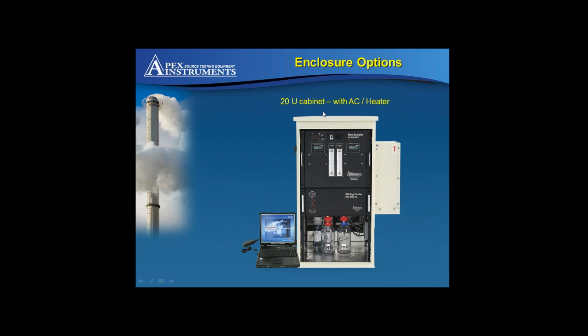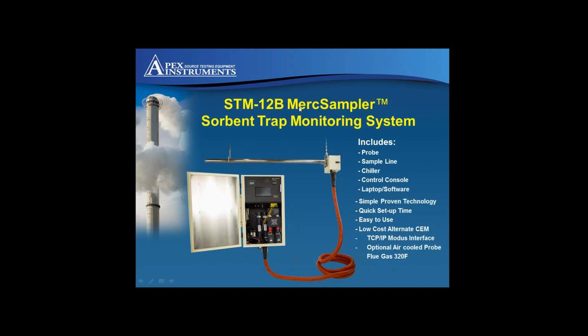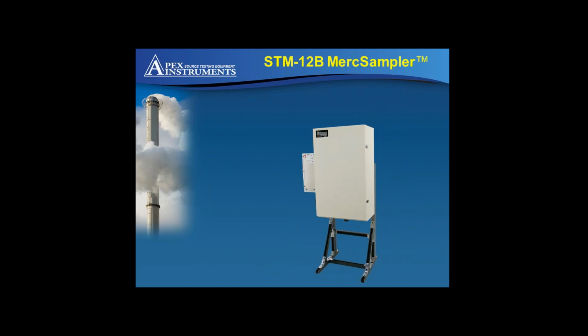Packaging of the sorbent trap control system. Generally we have 3 variations: a portable, a 20U enclosure and the wall or rack mounted unit. From a 20U housing, as previously seen, to the smaller footprint wall or stack mounted cabinet where space may be at a premium, or if space in the elevator accessing the sampling platform is an issue. We've listened to our customers and developed a smaller footprint rack or wall mounted control console, keeping the same functionality as our XC6000 units.